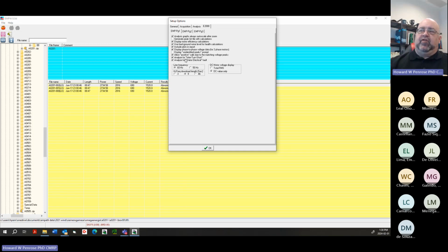These things down here, for what we're doing, do not change any of that. It doesn't matter whether you're in a 60 hertz or 50 hertz environment, just leave it as default. High frequency download length, leave it as 9. You'll start filtering out some of the things we're looking for if you select 46. It'll also double the amount of time it takes to collect data, which in the configuration I'm showing you is 48 seconds. Leave this one here as DC value only.